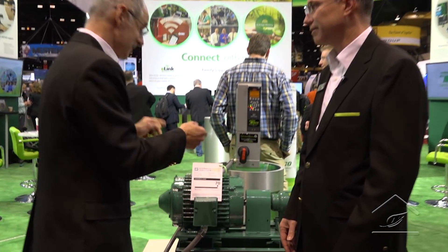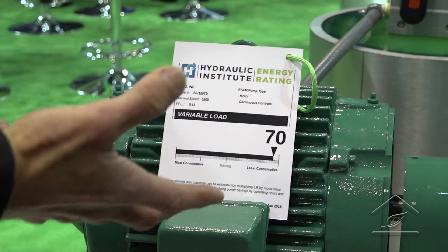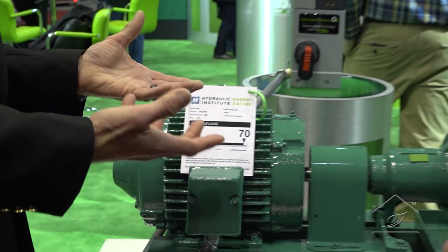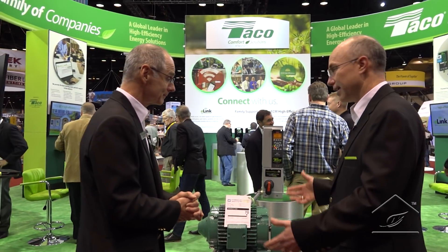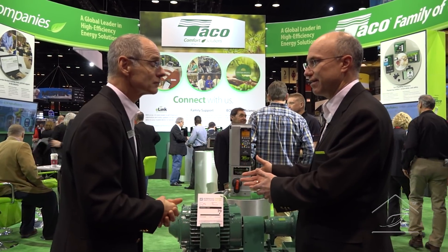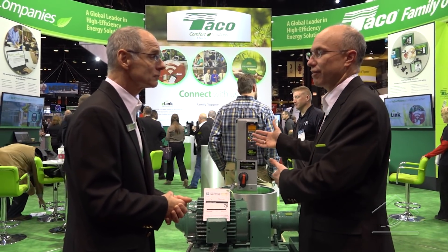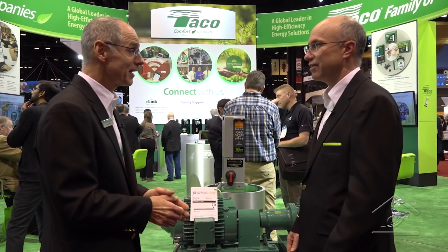This can really save some energy. You have a pump running at fixed speed, and now you put in something with ECM and system response with a characterized drive — the savings are incredible. On a 50 horsepower pump going to something with a variable speed drive, running about 4,000 hours a year, you're saving about $13,000 to $14,000 a year in energy savings.